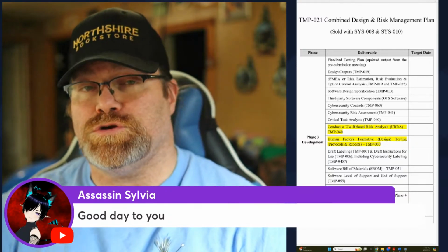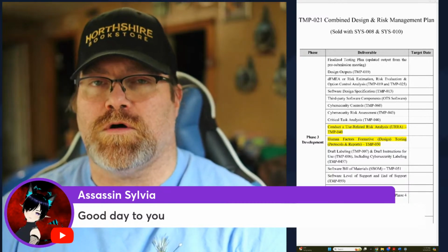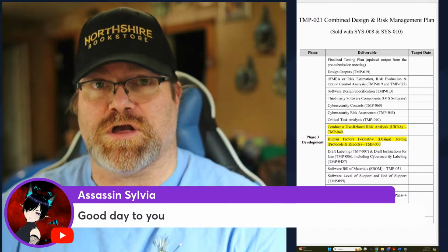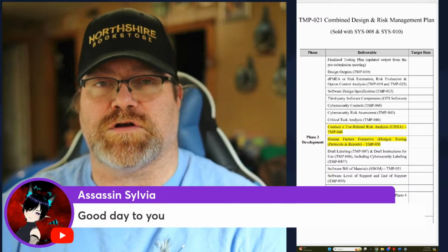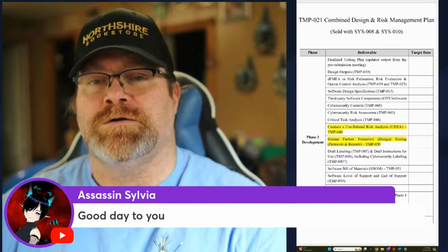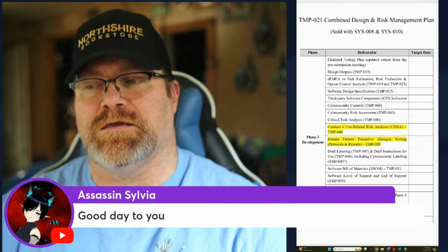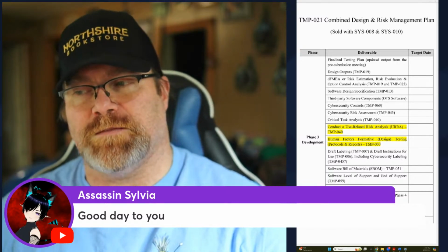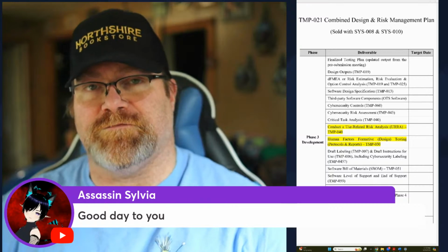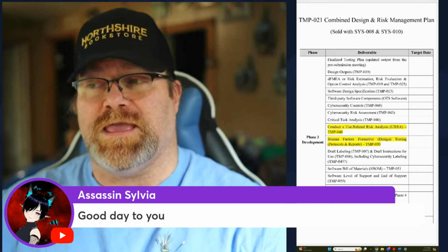But then when you do the summative validation, the final validation for human factors, you're going to want to do that on the final version of software, your final version of your instruction for use. And if you're doing it as part of a clinical study, you're going to want to make sure that you do it as part of that site initiation visit. So summative is going to be later. Formative is going to be in this development phase. There are other reasons why you would do the formative in this phase.